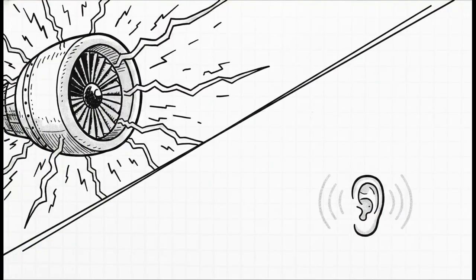To really get how we solve this, we've got to grasp the sheer scale of the power we're dealing with. It explains exactly why our sensitive, highly calibrated equipment absolutely requires a middleman. Think about these voltage levels. We're talking 11,000 volts, 33,000 volts, and even up to 132,000 volts. These transmission lines are speaking a language of pure roaring power. It's a screaming, high-voltage language that is just way too chaotic and dangerous for standard relays and meters to even comprehend, let alone survive. If a standard meter operates at the volume of a polite conversation, these grid voltages, they're basically a jet engine at takeoff.